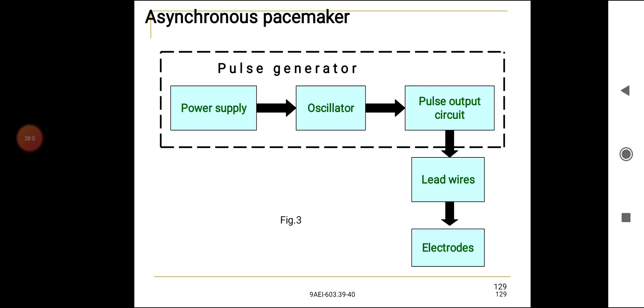The pulse output circuit is connected to the lead wires. The lead wires are connected to the electrodes. The electrodes are arranged on the heart. An asynchronous pacemaker consists of a power supply, oscillator, pulse output circuit, lead wires and electrodes.